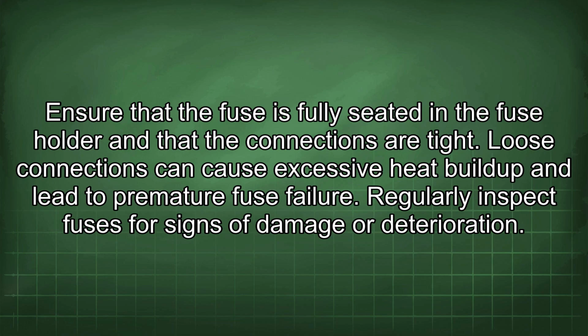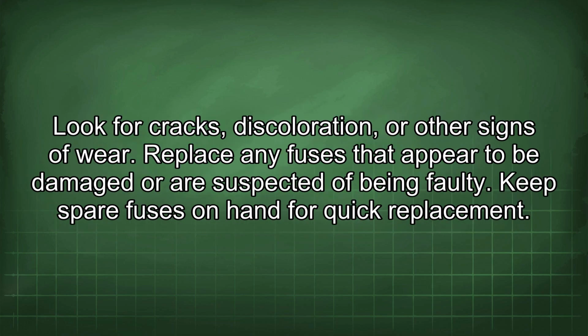Ensure that the fuse is fully seated in the fuse holder and that the connections are tight. Loose connections can cause excessive heat buildup and lead to premature fuse failure. Regularly inspect fuses for signs of damage or deterioration. Look for cracks, discoloration, or other signs of wear. Replace any fuses that appear to be damaged or are suspected of being faulty.